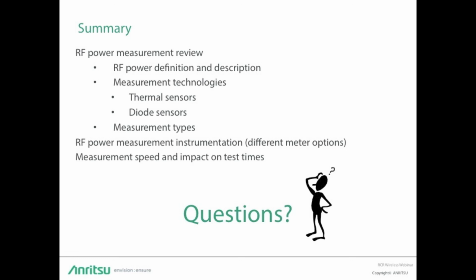PowerXpert, the software application you mentioned earlier, seems pretty intuitive, but can one program the sensor directly for automated test? Yeah, actually, that capability is there. As a matter of fact, our new 200 series power sensors were designed very specifically with this high volume manufacturing usage in mind. Knowing that speed is a key factor in that case, they can be programmed using the programmable commands that way as well.